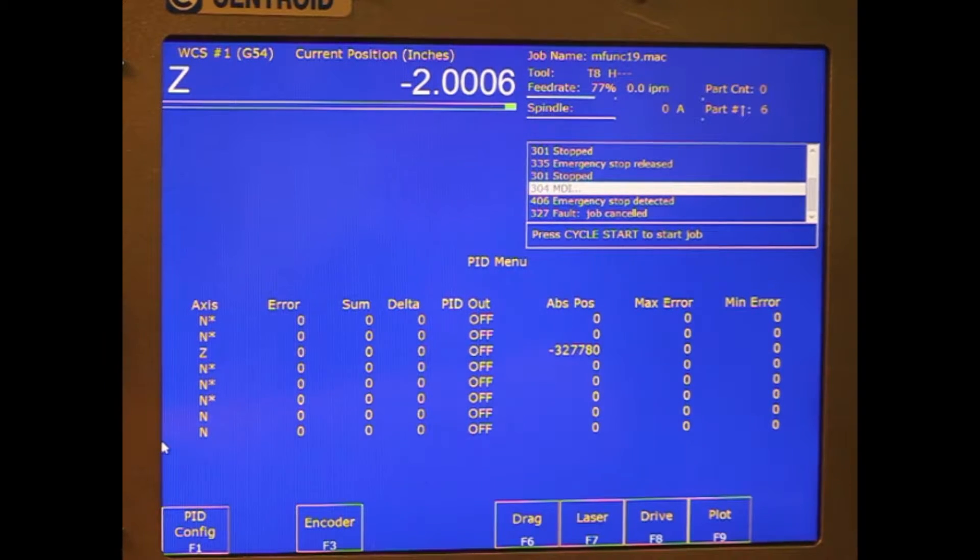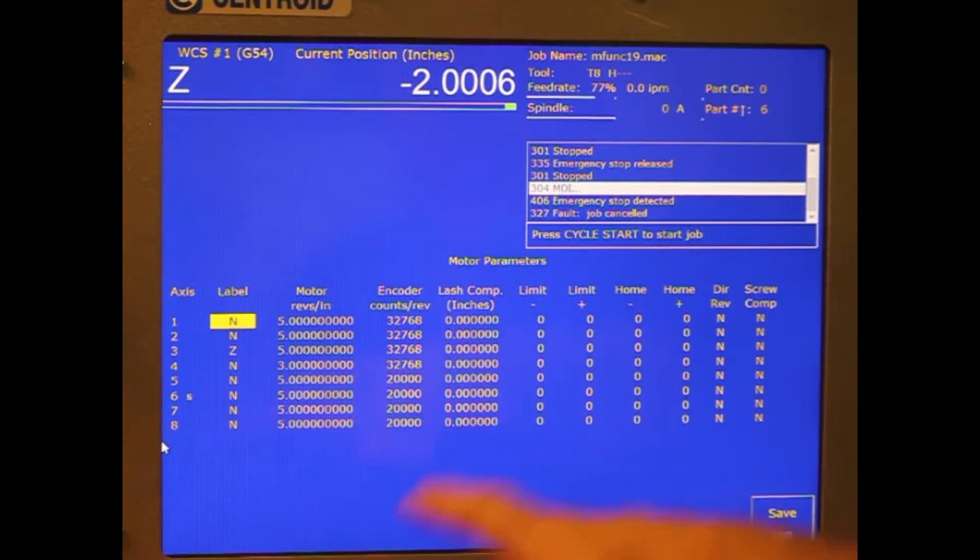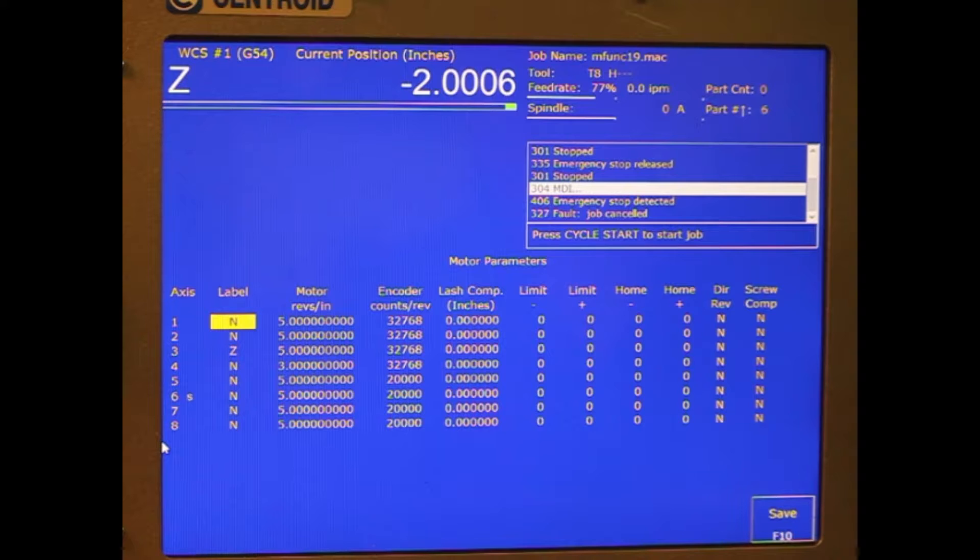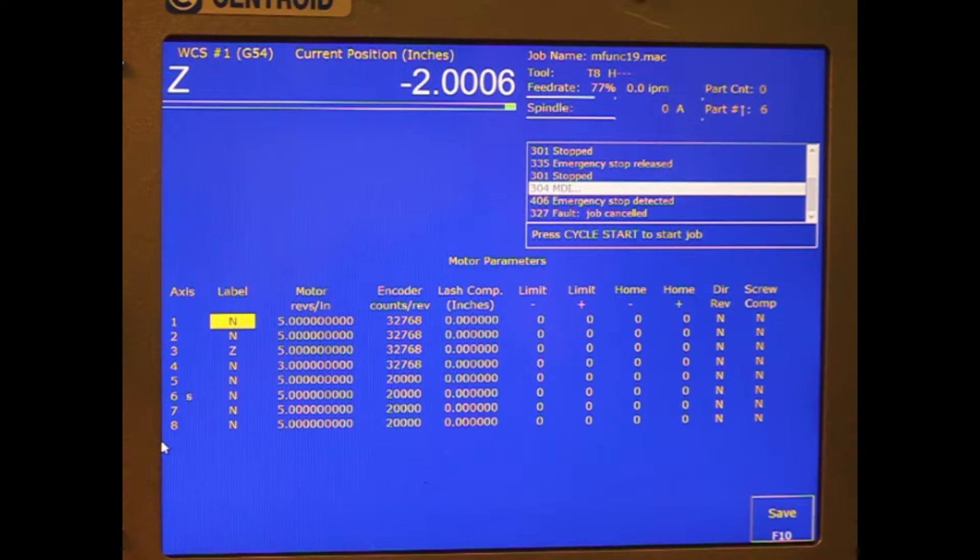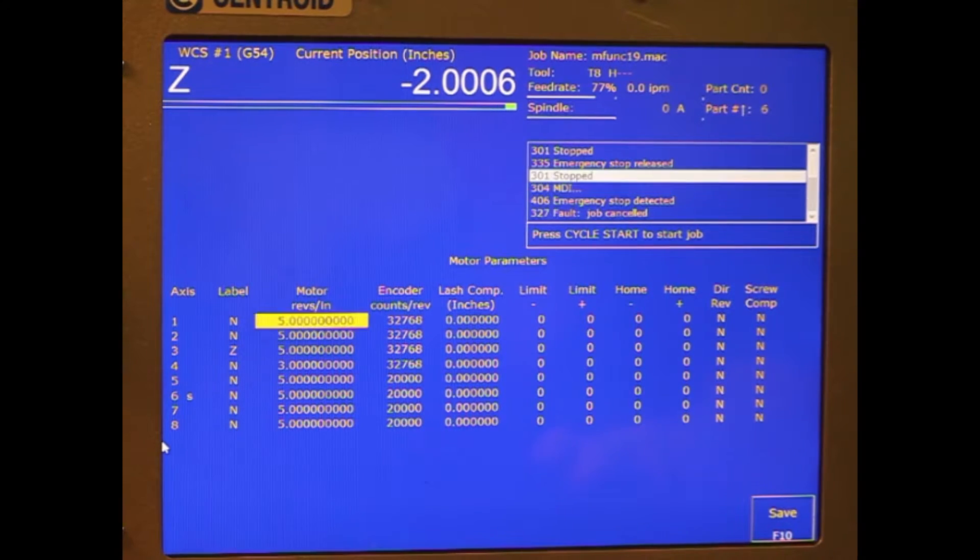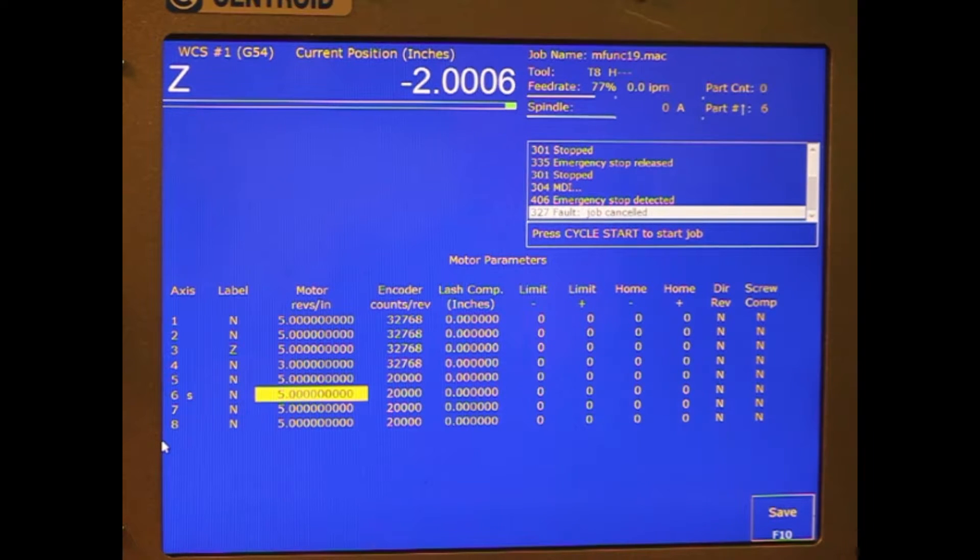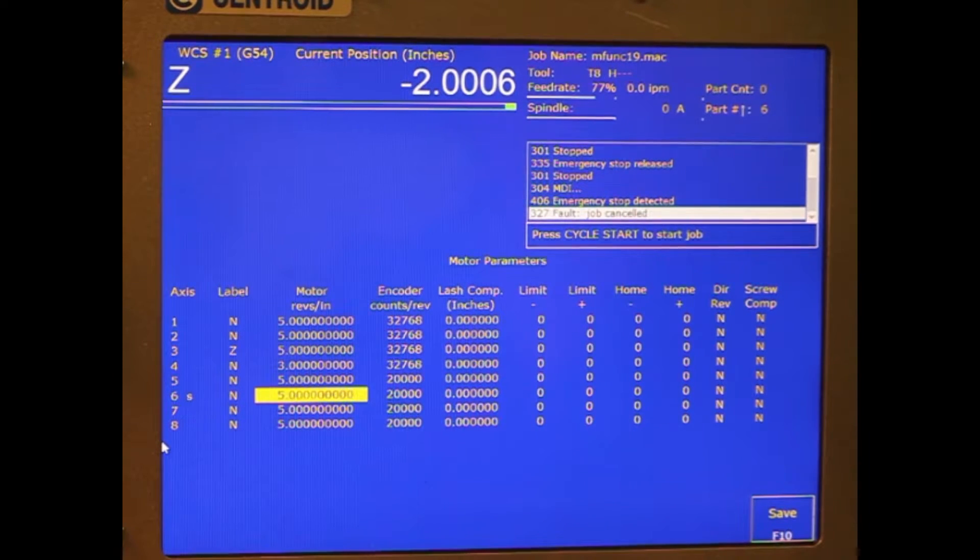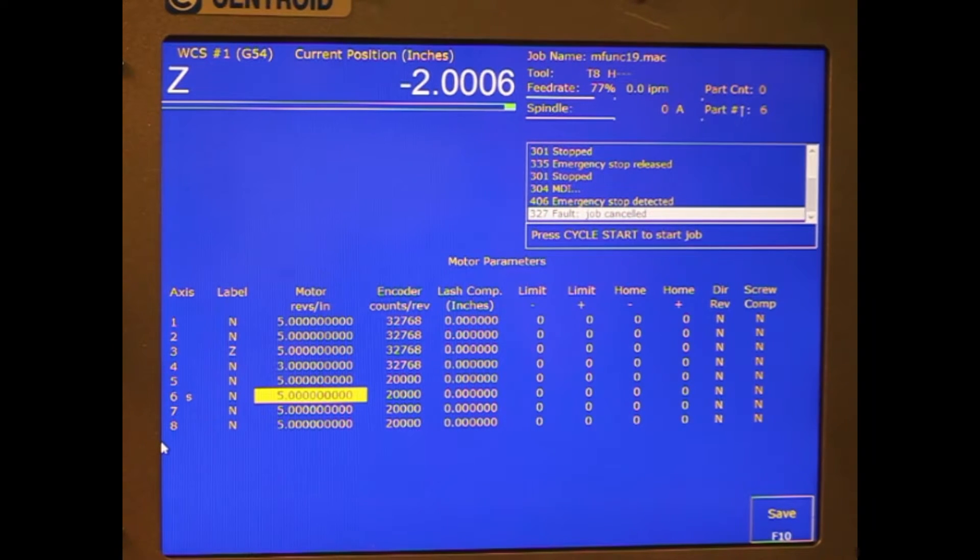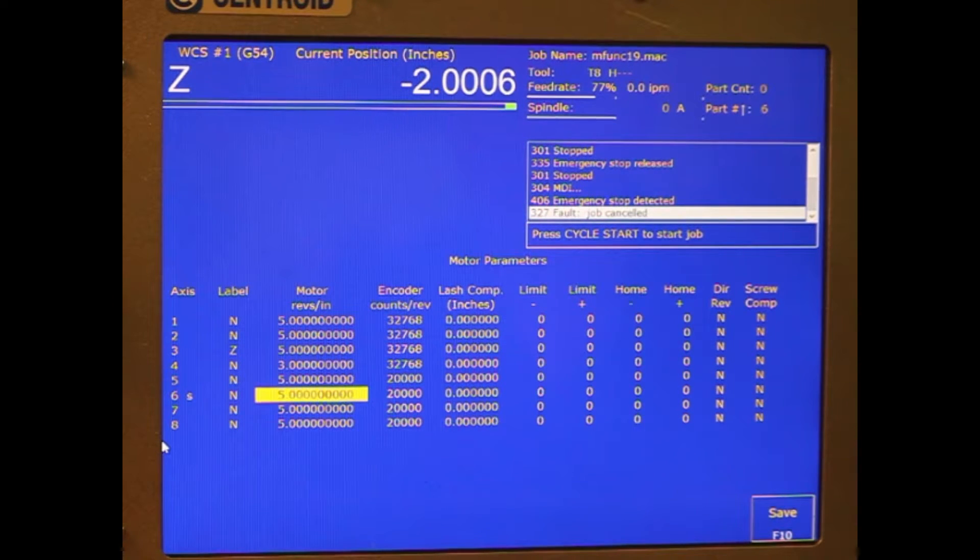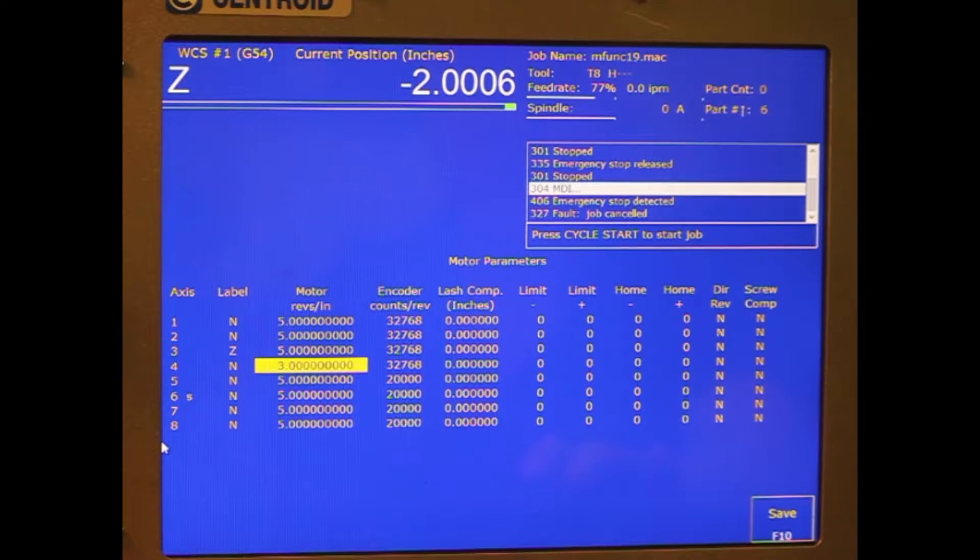This one's 32768, which we set in here, which is an 8192 count encoder. Quadded means times four, and it gives you 32768. The other one we need to set up is the motor revs per inch. You're just going to have to turn the motor basically one revolution, see how much it moves in one revolution. Through math, you can backward calculate that to see how many revolutions of the motor it takes to move one inch.